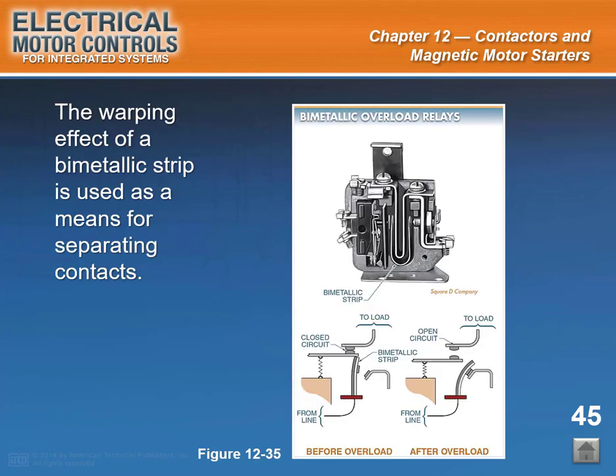Start of slide 45. Slide caption: The warping effect of a bimetallic strip is used as a means for separating contacts. See Figure 12-35. In certain applications such as walk-in coolers, remote pumping stations, and some chemical process equipment, overload relays that reset automatically to keep the unit operating up to the last possible moment may be required. A bimetallic overload relay is an overload relay that resets automatically.